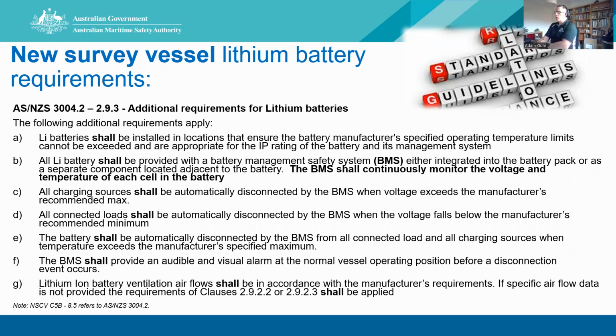Self-explanatory. All lithium batteries shall be provided with a battery management system. And you'll notice there's a lot of shalls in these standards, so you must. It's either integrated into the battery pack or it's a separate component located adjacent nearby. The BMS shall continuously monitor voltage, and the versions don't do each cell. They just monitor the region, the area.